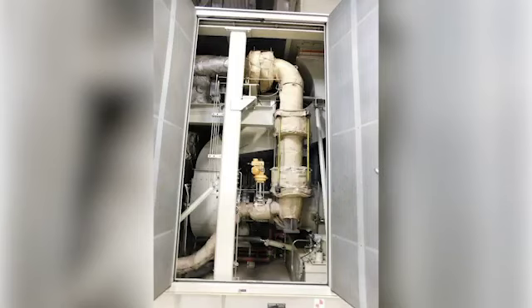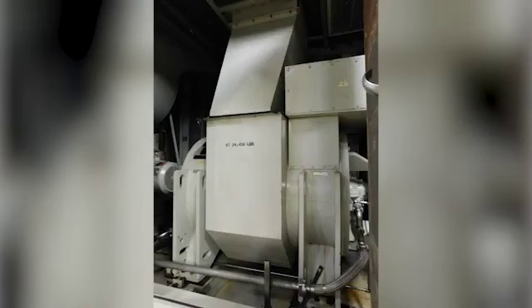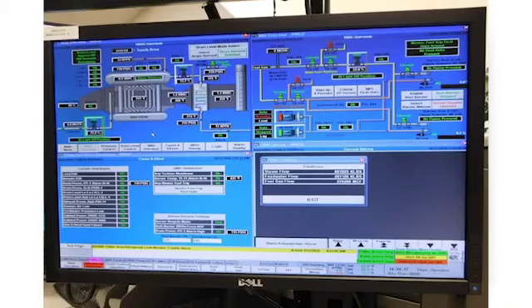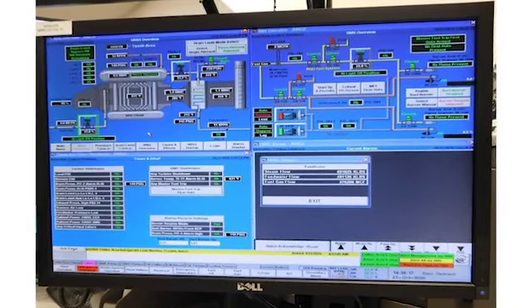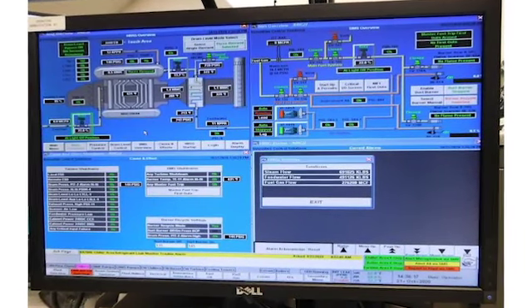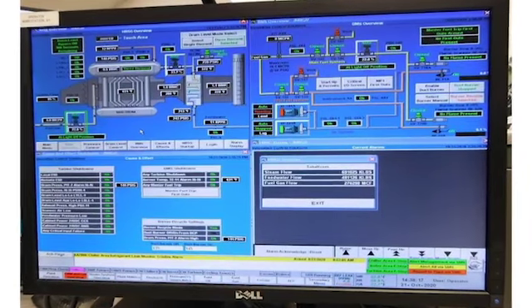Quick shot here of the Mercury 50 compressor. This is where it takes in the air and compresses it to the required pressure before we send it to the burners. And then we have the generator set, which is actually a Kato generator, probably roughly a 5,000 kVA unit that's attached to the York epicyclic gear. Altogether it ties into a really awesome little package that has served us extremely well, with our uptimes being in the high 90s. Take a quick shot of the Heatec heat recovery steam generator HMI here, and you'll see that even though it is a once-through type boiler, it is a water tube boiler.